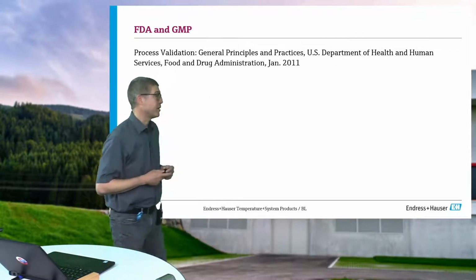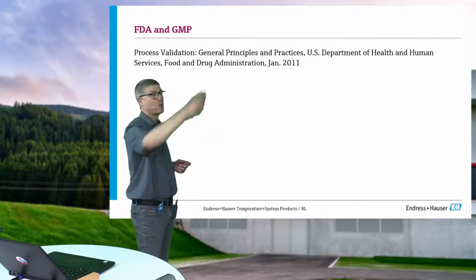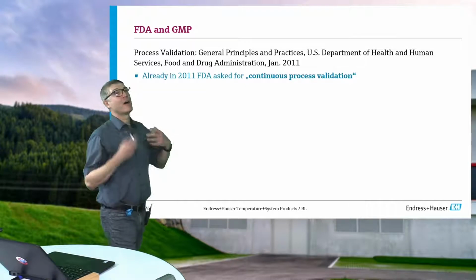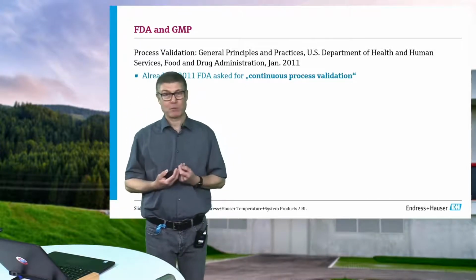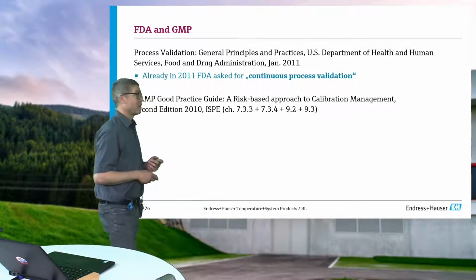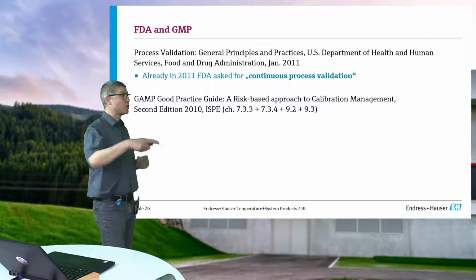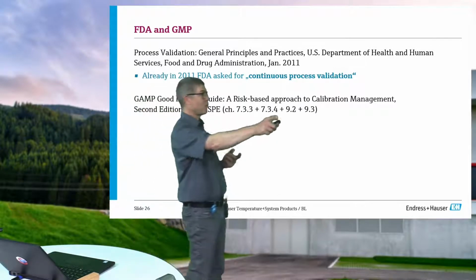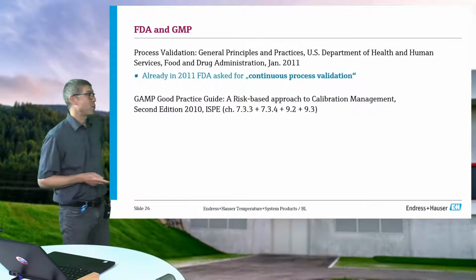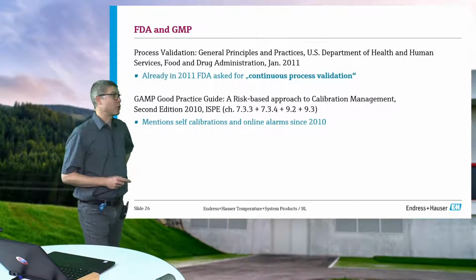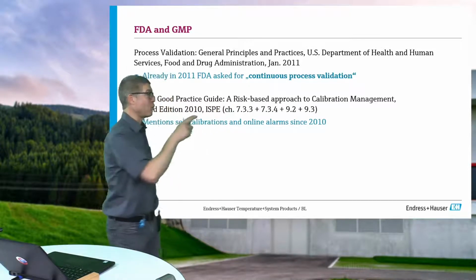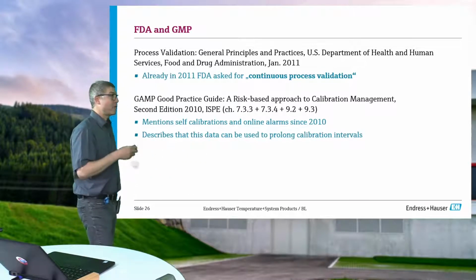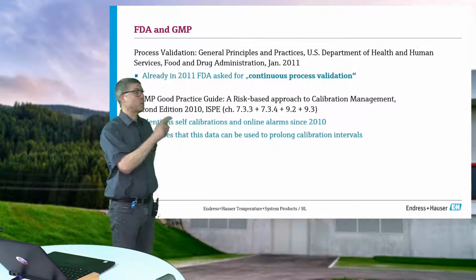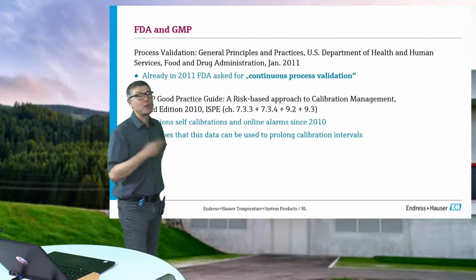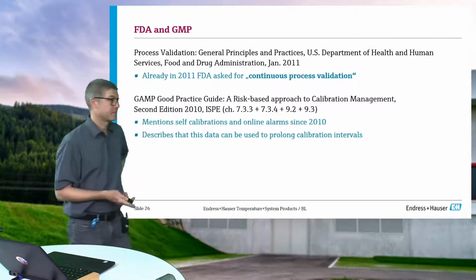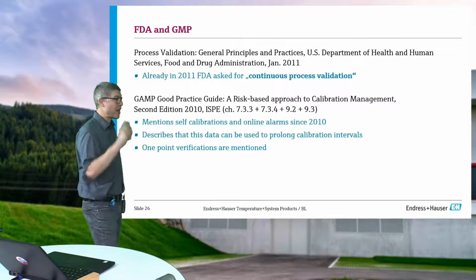And I have the sources here. The process validation general principles from 2011 says use continuous process validation if possible. The GAMP good practice guide about calibration management, and here you see the chapters. You can look to it if you are familiar with this rule. It says self-calibrations and online alarms, stated in a document from 2010. It describes that these data, determined by these self-calibrations and online alarms, can be used to make the calibration intervals longer. And also 1-point verifications are mentioned.